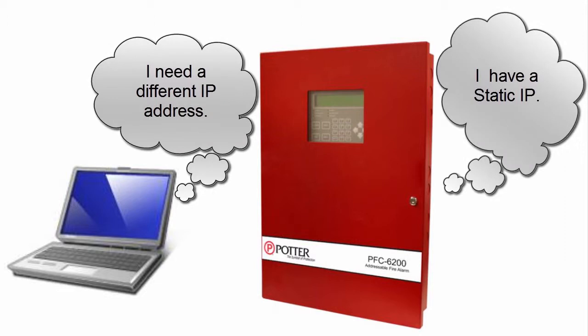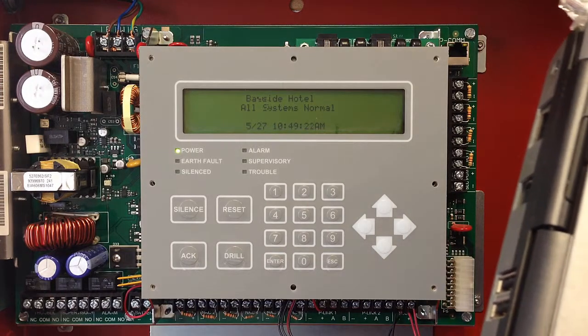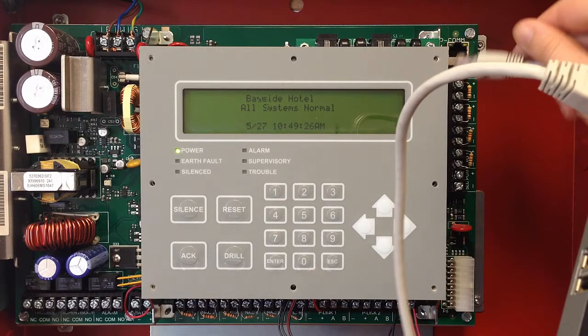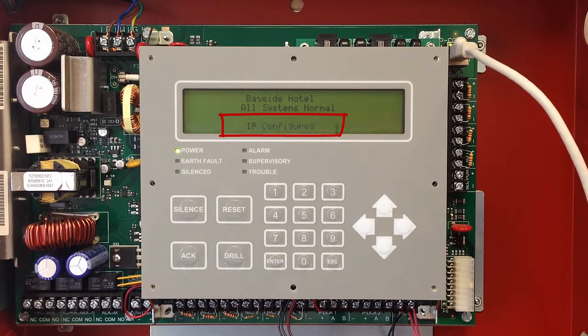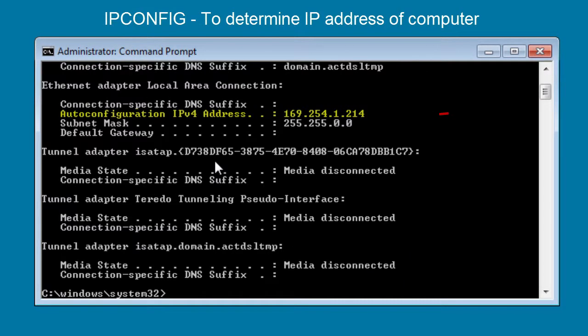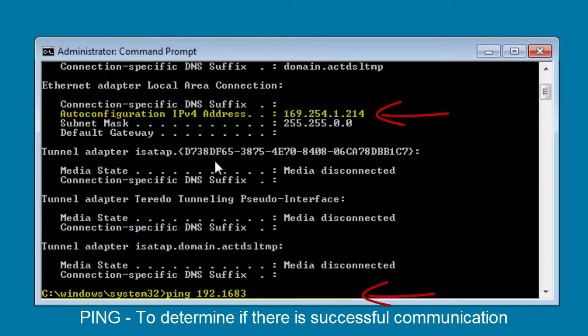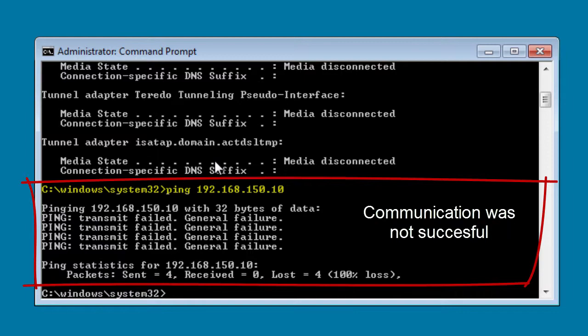If a static IP address has been set at the fire alarm control panel, you may need to set a static IP at your laptop computer in order to communicate successfully. When you direct connect from your laptop computer to the fire alarm control panel, the fire alarm control panel will tell you the IP address. In this case, you can see the IP address of my fire alarm control panel when direct connected is 192.168.150.10 — it no longer has that private network IP address. A static IP address has been assigned to this fire alarm control panel. If your laptop computer does not have a similar IP address, a static IP address will need to be assigned to it. You can check the IP address of your laptop by bringing up the command prompt and typing ipconfig, and check for successful communication by pinging the IP address shown on the fire alarm control panel: 192.168.150.10.